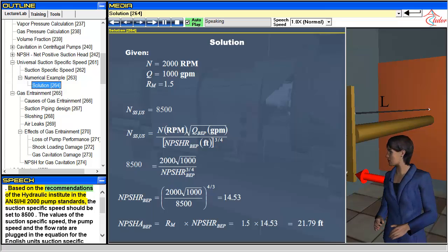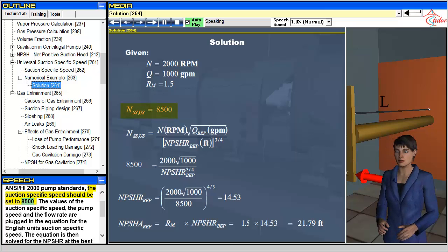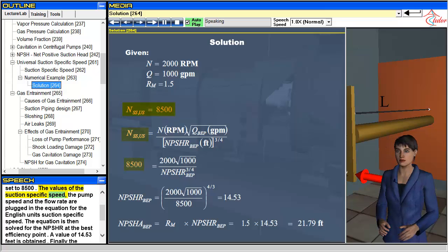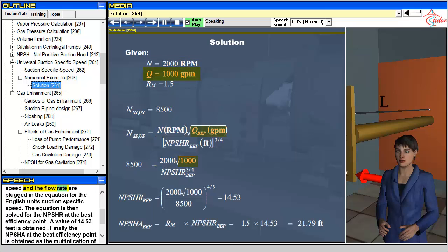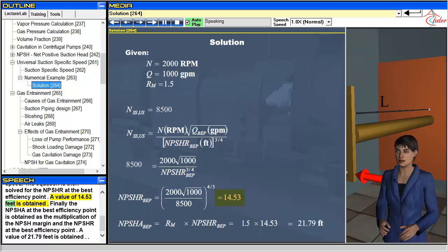Based on the recommendations of the Hydraulic Institute in the ANSI/HI-2000 pump standards, the suction-specific speed should be set to 8,500. The values of the suction-specific speed, the pump speed, and the flow rate are plugged into the equation for the English unit's suction-specific speed. The equation is then solved for the NPSHR at the best efficiency point. A value of 14.53 feet is obtained. Finally, the NPSHA at the best efficiency point is obtained as the multiplication of the NPSH margin and the NPSHR at the best efficiency point. A value of 21.79 feet is obtained.